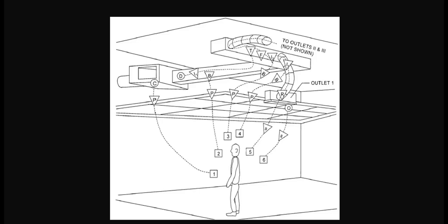The fourth is a breakout on the branch connection. This is the same path as 3, but with an added insertion loss at the connection and different breakout attenuation properties due to it being flex duct. The fifth is the full discharge path to include duct end reflection loss and the space attenuation between the discharge location and the perceiver. The final is the outlet generated path that begins at the outlet and is attenuated by the space between the outlet and the perceiver.